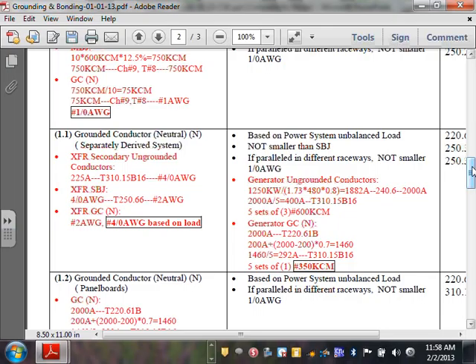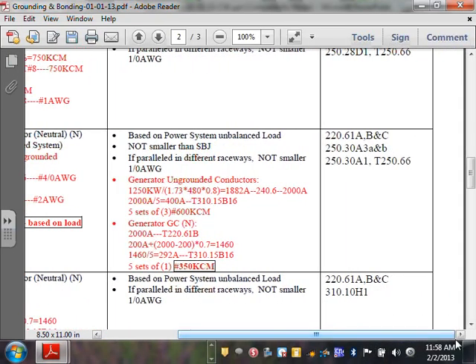So slightly lower. Can you explain why you took 200 amps and subtracted out 200 amps? Because the code says, and that's really even very conservative, if you go to 220.61 A, B, and C, it says take your neutral load. If your neutral load is higher than 200 amp, you can apply more derating to it, which is 70%. So the first 200 amp, don't derate, leave them alone. Anything higher than 200 amp, cut them by 0.7. That's directly from 220.61A. Unless it's harmonic, then you can't do it.